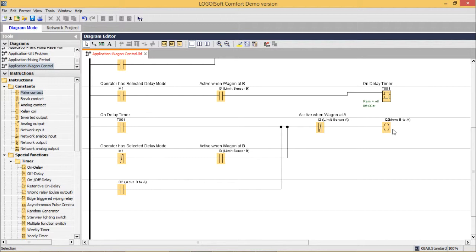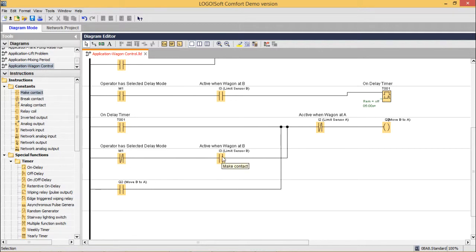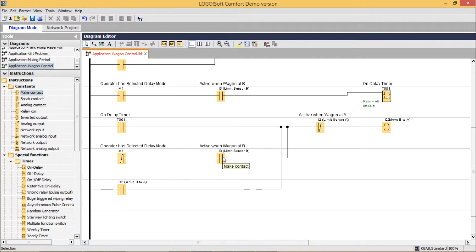For the B to A movement: in delay mode, when the timer is on after 5 seconds Q2 activates and remains on until limit sensor A is sensed. In the non-delay mode, M1 is not selected (break contact) and the wagon is at limit sensor B, so move B to A is initiated immediately. A parallel latch ensures Q2 remains on even after the wagon leaves sensor B, until the wagon reaches limit sensor A. That is the complete description of the ladder diagram.